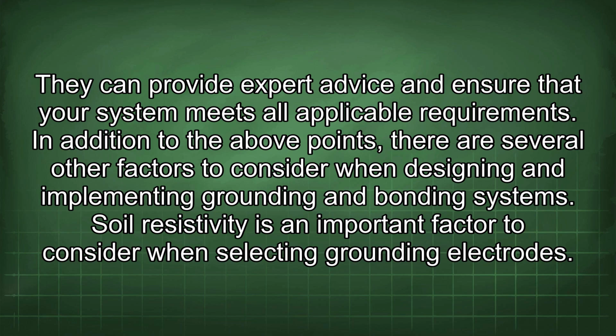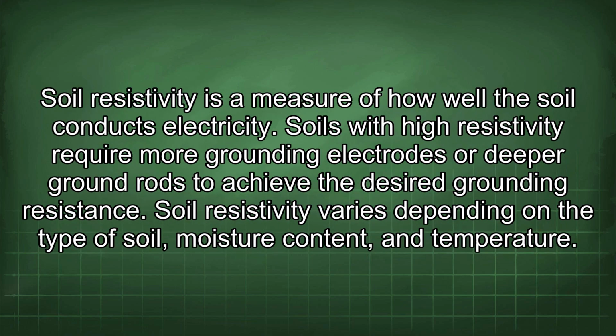In addition to the above points, there are several other factors to consider when designing and implementing grounding and bonding systems. Soil resistivity is an important factor to consider when selecting grounding electrodes. Soil resistivity is a measure of how well the soil conducts electricity. Soils with high resistivity require more grounding electrodes or deeper ground rods to achieve the desired grounding resistance. Soil resistivity varies depending on the type of soil, moisture content, and temperature.